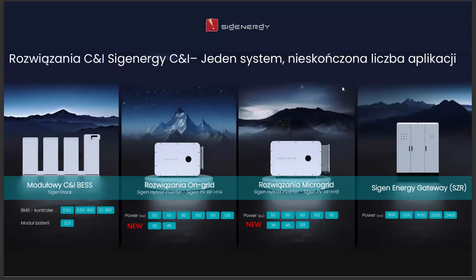Our system is highly flexible. Flexible CT selection. You can use our meter and match it with suitable 5A current transformers. Rogowski coils. If installation conditions require measurement without disconnecting busbars, the system can also work with Rogowski coils. Even in LV/MV transformer environments, we can meter the system effectively on the low voltage side, so the platform sees the real building energy balance and manages battery charging accordingly.